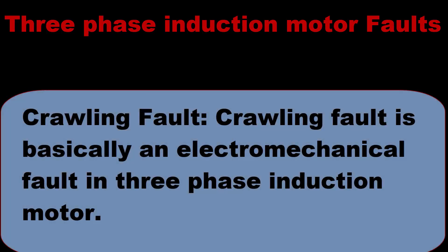Crawling fault: this is basically an electromechanical fault in a three-phase induction motor. This fault occurs when the motor is fully loaded with full supply voltages — it does accelerate, but runs at nearly one seventh of its synchronous speed. This specific phenomenon of an induction motor is called crawling.